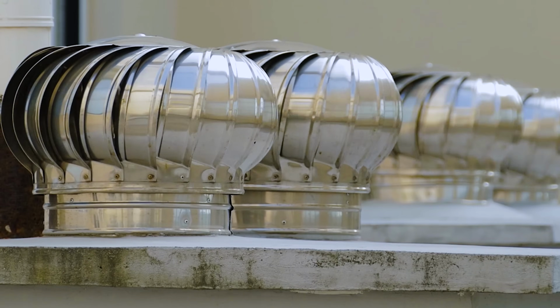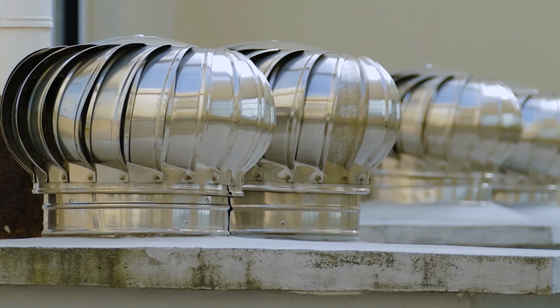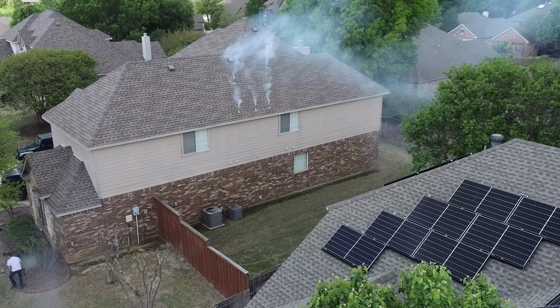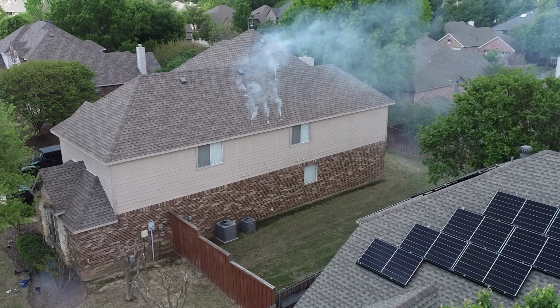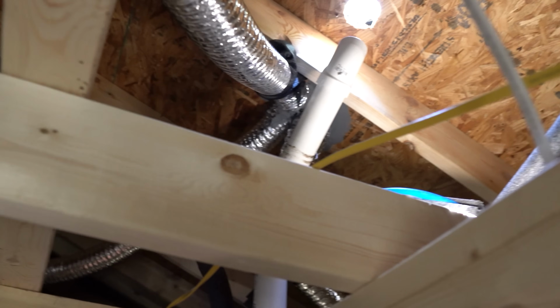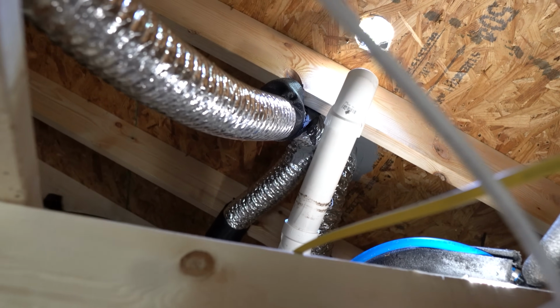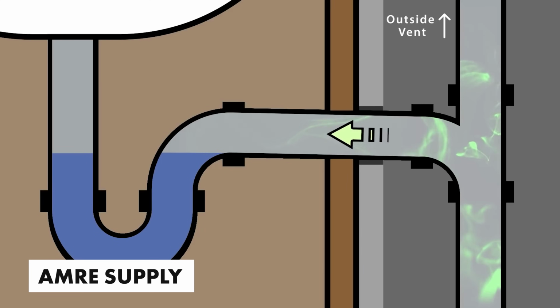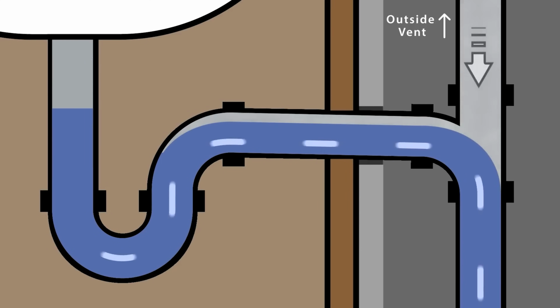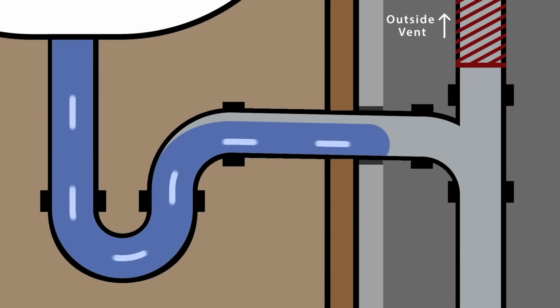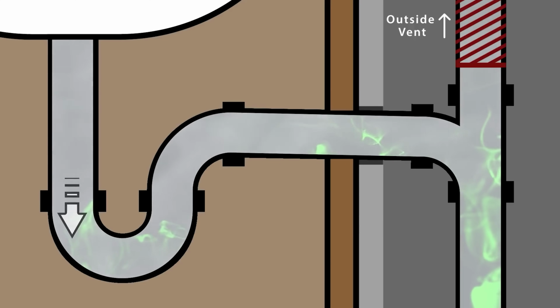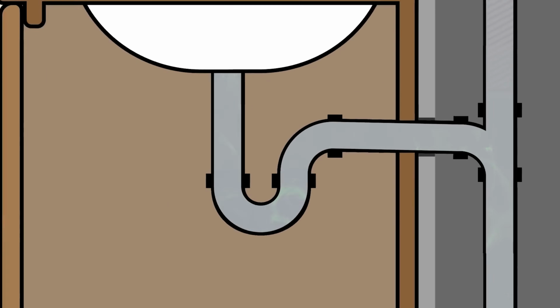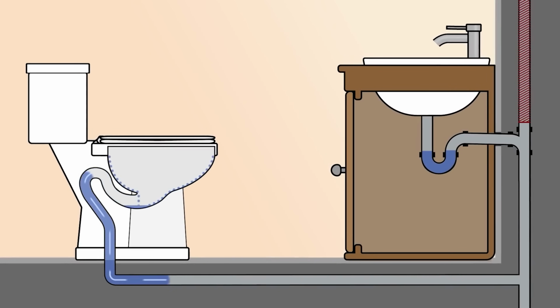Number two, unvented traps. Failing to vent traps properly can result in sewer gases entering the home, which is both unpleasant and hazardous. Now, improper vents are bad. If there's not a vent, or the vent's clogged, or it wasn't run right, now it's got water in it, there's a lot of different things that can make that happen, but it can cause that P-trap to dry out if there is a P-trap. So unvented, it's not a good way to do it.